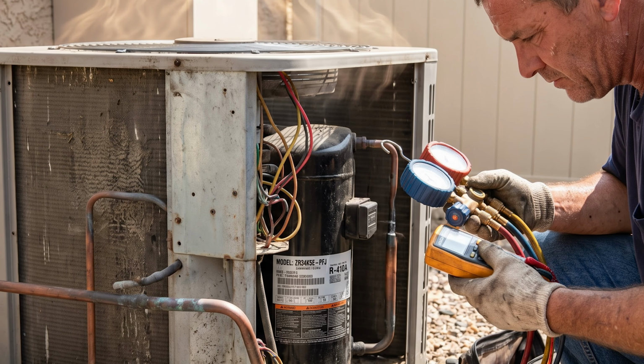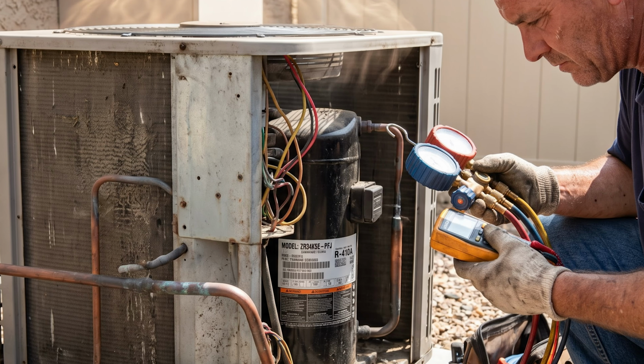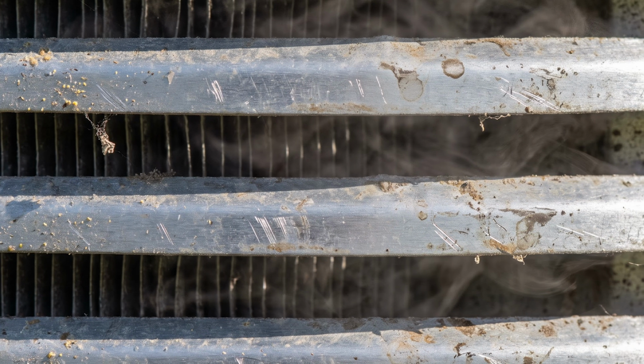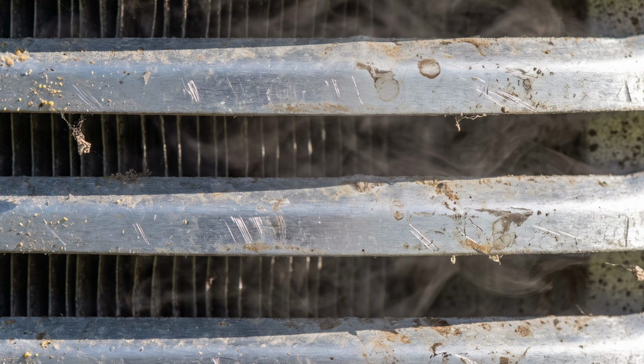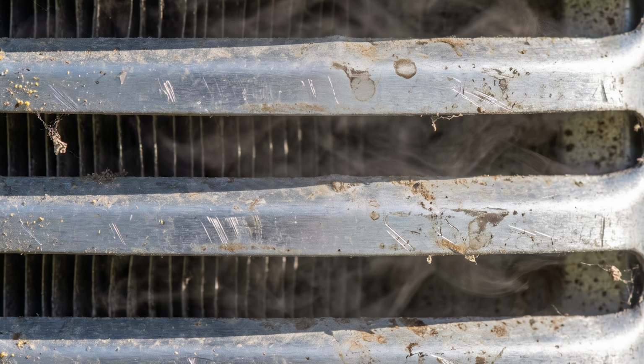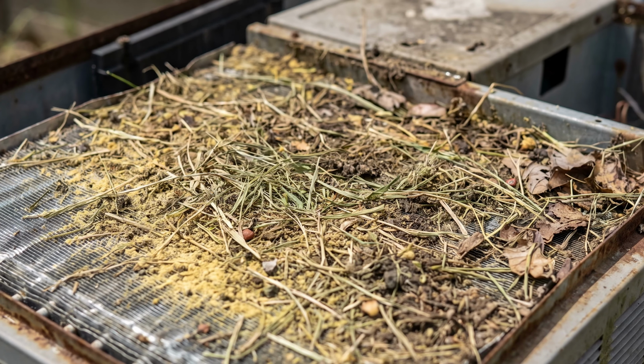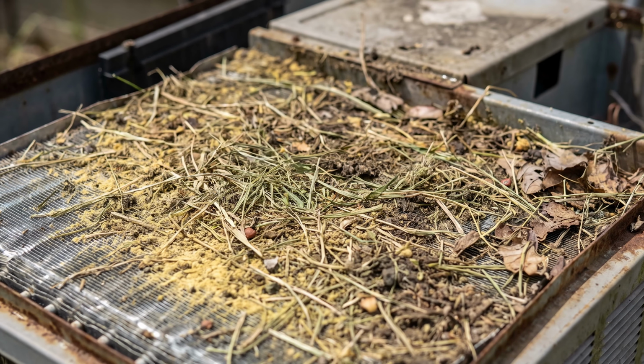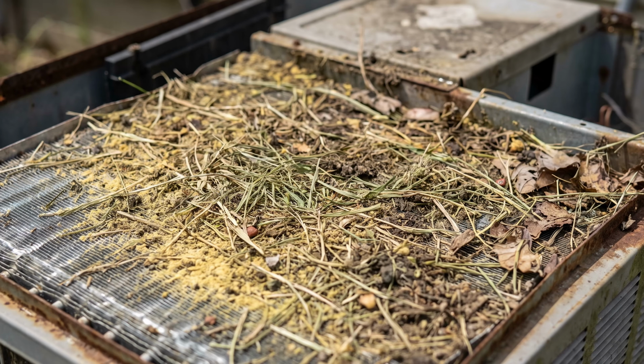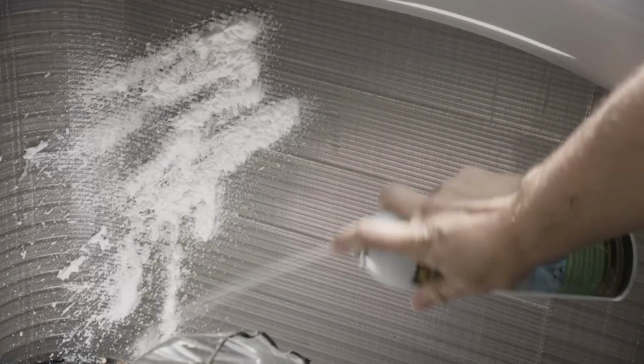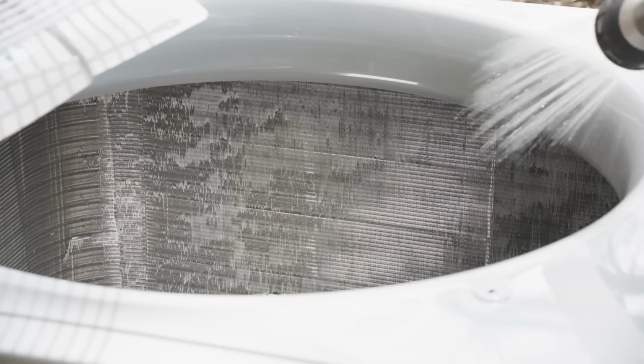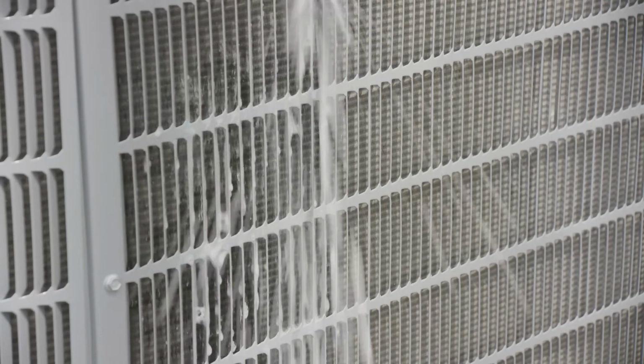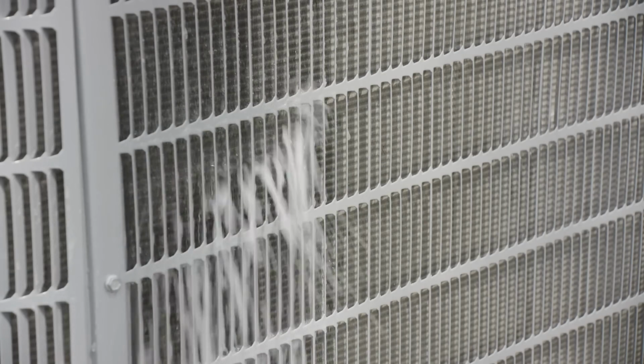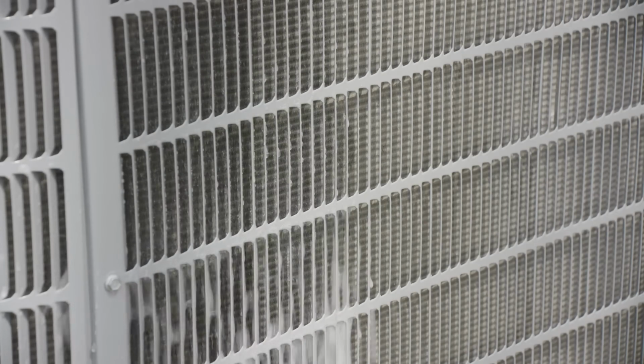Even if you don't hide your unit behind a fence, you might still be suffocating it. Throughout the spring and summer, the condenser acts like a giant vacuum cleaner. It pulls in grass clippings, dandelion seeds, dog hair, and dirt. Over a few months, this creates a thick blanket of debris perfectly covering the tiny metal cooling fins. The fix for this takes 5 minutes and costs absolutely nothing. Once a month during the summer, take a standard garden hose, put on a gentle spray nozzle, and wash the dirt and pollen off the outside of the machine.